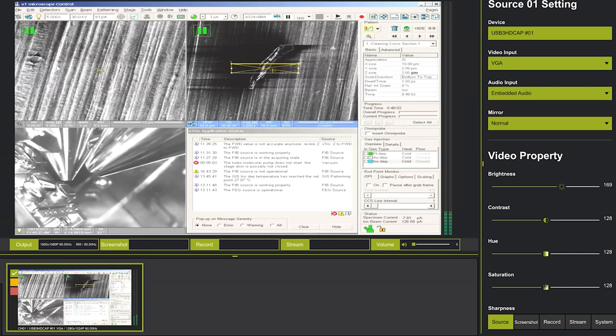If I ask the instrument to remove 10 by 2 by 2 micrometers with the current condition, it says it's going to take 48 minutes. That's too long, so what I'm going to do is increase the ion beam current to 2.8 nanoamps - actual measurement is about 3 nanoamps. Now it's going to take a minute and a half, less than 2 minutes. Let's check it first.